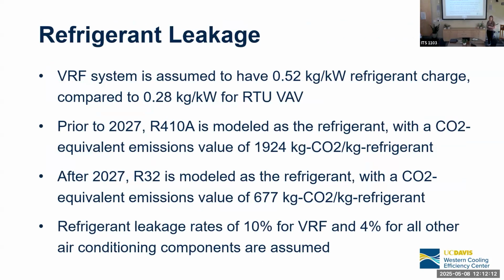In the literature, there are a lot of different leakage rates reported in our paper, which hopefully you'll be able to access in the next few months. We did a sensitivity analysis, but here you're just going to see results for 10% leakage rate for VRF and 4% for all the other systems, so the DOAS air conditioning and the rooftop air conditioning. Prior to 2027, we're using R410A, so with the AIM Act 2020, after 2027, low GWP refrigerants are required, so we're switching to R32 in our modeling after that.